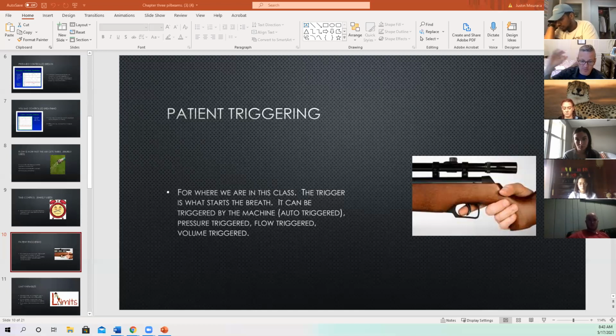Pressure triggering is if there's centimeters of water pressure baseline in there, I have a PEEP set at 5, and then the trigger set at -2. That means I have to drop down to 3. All right, so that patient has to suck back 2 centimeters of water pressure out of the system, and then the ventilator will cycle. It's a little harder to do. So the patient has to work a little bit harder before they get a breath. Do we want them to have a hard time doing that? Absolutely not, right? Because they become desynchronous with the ventilator.